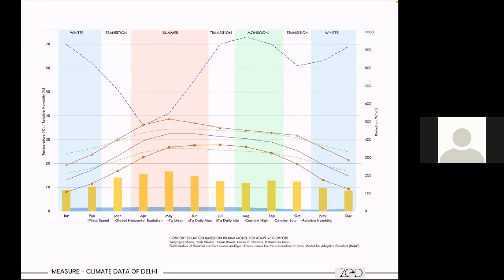We chose to go with an adaptive comfort thermal graph to extend the comfort zone and challenged the basic idea of air conditioning. Looking at the adaptive comfort graph, during the summer period the delta T was not more than 8 to 10 degrees, and even at 45 degrees it was not more than 15 degrees. During the monsoon and winter seasons, because of the adaptive comfort thermal zone, the performance of the building was pretty much within the comfort zone. Hence, free cooling and intelligent planning can come into picture to lower down the heating and cooling demand.